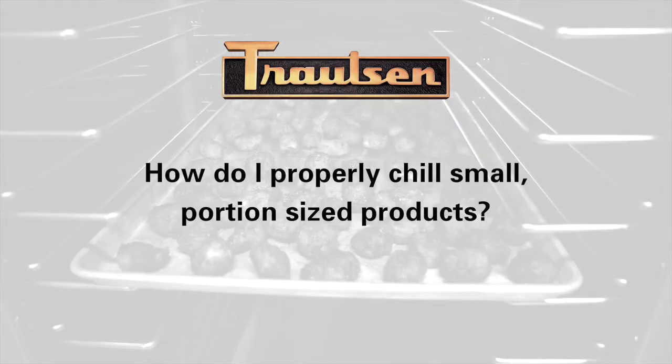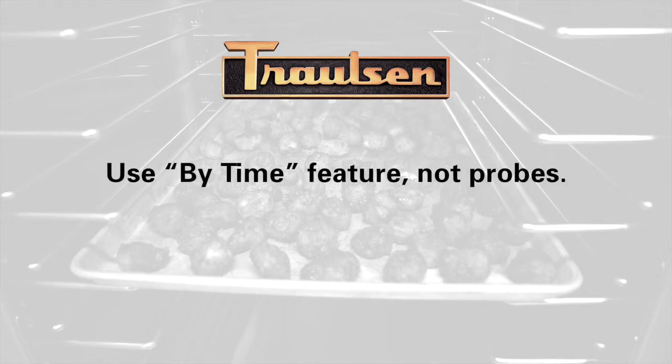How do I properly chill small, portion-sized products? Small products are often best chilled without probes using the By Time feature. Using test batches, it can be determined in advance how much time is required to safely chill a given product load. This can then be duplicated in actual use and verified afterwards using a handheld thermometer and then documented.